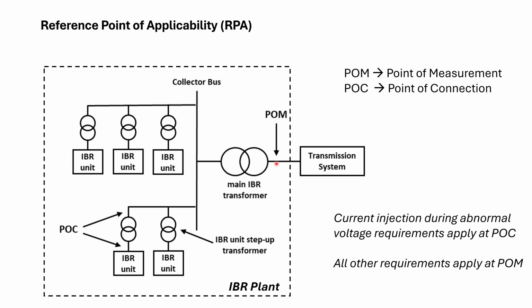However, the current injection requirements during a voltage ride-through are going to be applicable at the point of connection, which can be thought of as the IBR terminals. It could also be the high side of the IBR unit step-up transformer. The delineation there is basically how the IBR unit is type tested. But for the purposes here, we can just think of it as the IBR unit or the inverter terminals.